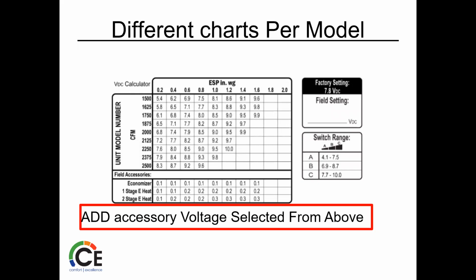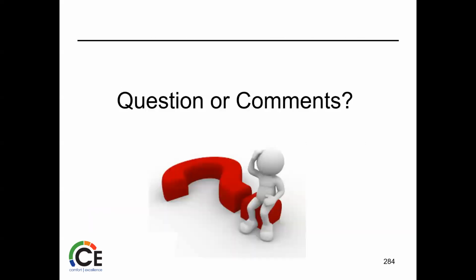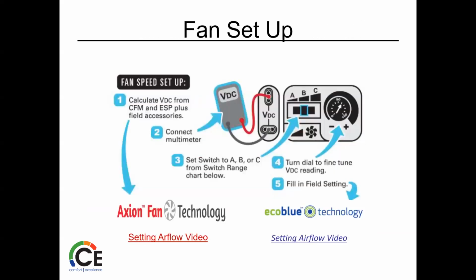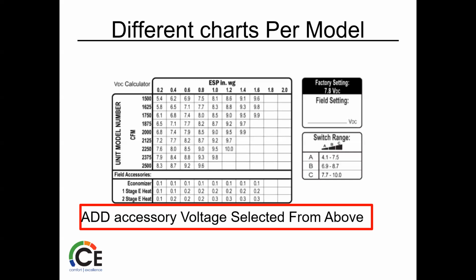So once you figure that out, you use this chart. Okay, whatever CFM you want? If you want 2000 and you got a 1.0 ESP, you go across 2000, it says 9.0. If there's an economizer or electric heat, we add a little bit here. We've got a variable that you add. And then you come back here with your meter hooked up. You turn this potentiometer till it says 9.0 or 9.1 or whatever you end up needing. You look at your selection switch here. All right, I need 9.0, so I have to be in range C, and you are done. That fan is set up for 2000 CFM, and you're rocking and rolling.